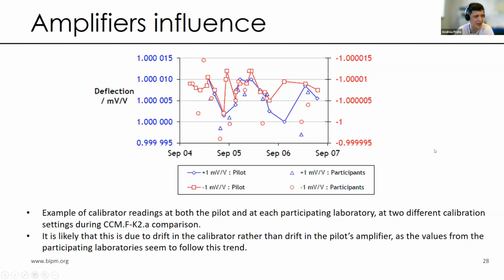So this was fine in CCM.F-K2.a comparison, and this is mainly due to the drift of the calibrator itself. So we consider the calibrator stable in time. Instead, we can see that also the calibrator has different behavior and a drift in time. So basically, it might be less stable than the amplifier itself.